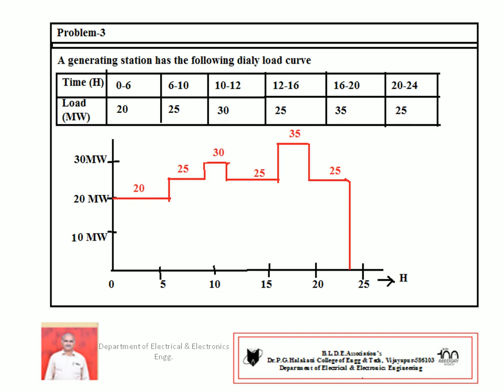Similarly, how many units are generated per day, you have to calculate, in kilowatt hour per day. Units generated per day is equal to the area under the load curve. You calculate the whole area of the graph you plotted, that itself is the units generated. That means for each load, you consider how many hours it operates. 20 megawatt operates for 6 hours, so 20 into 6. Then 25 megawatt operates for 4 hours, 25 into 4. Next 30 megawatt operates for 2 hours, hence 30 into 2. Again 25 megawatt operates for 4 hours, 35 megawatt for 4 hours, 20 megawatt... 25 megawatt for 4 hours. You multiply the respective time and respective load, hence you get the total. It is in megawatt hour. Getting the idea? Understand properly.